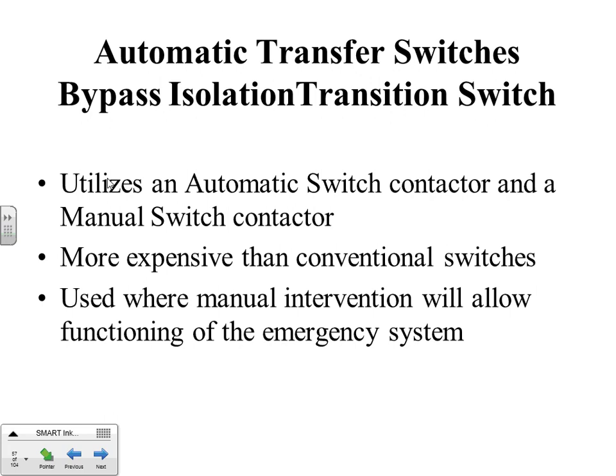Moving up the chain, bypass isolation transfer switch. This came about basically, I think it was in California. It's an expensive switch in that it bypasses the automatic contactor with a manual contactor. It allows the automatic portion to be worked on. Say it failed while an operation was going on at a hospital. That would allow the doctor to continue on emergency power if there were a problem with the transfer switch.